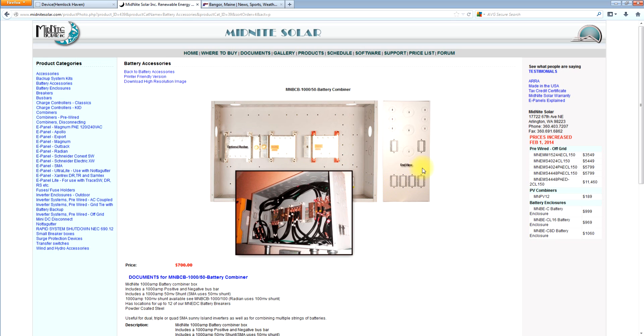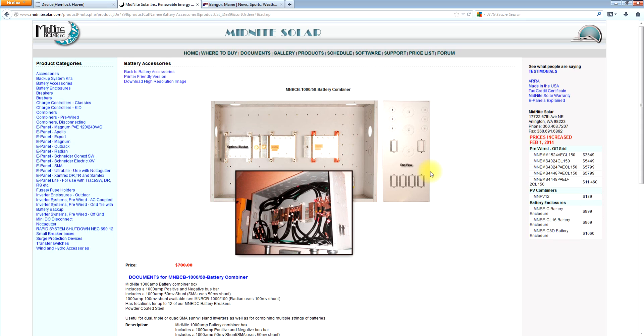And another unique feature of this box is it has twelve of these knockouts over here that allow you to put battery breakers in. So let's say you've got six strings of batteries and you want overcurrent protection on each string. You can put breakers in here and protect those strings of batteries, just like you would a combiner box for PV. And the knockouts as you see them are made for our MNE DC 125, 175 or 250 amp breakers. They will work with our MNE DC 5 amp through 100 amp breakers, but you will need the breaker adapter in order to make them fit in the box.